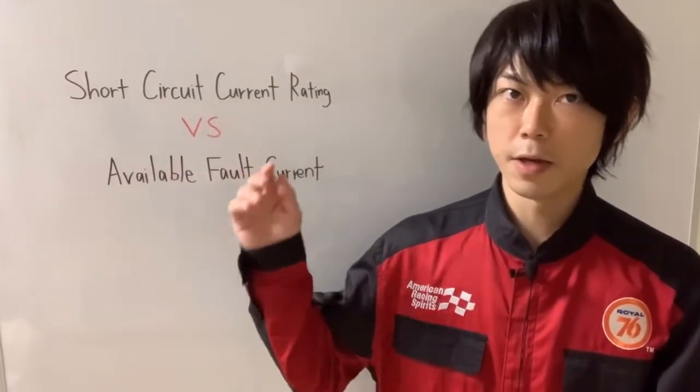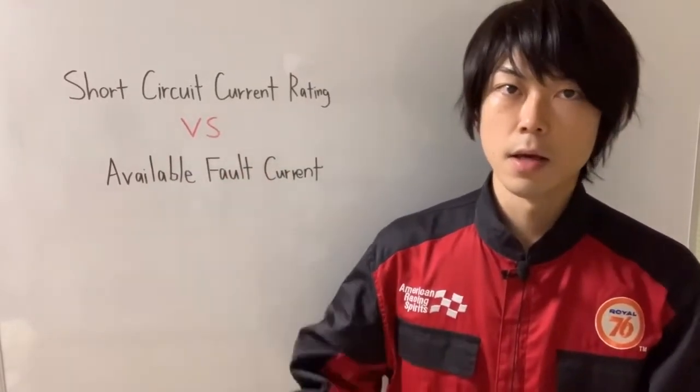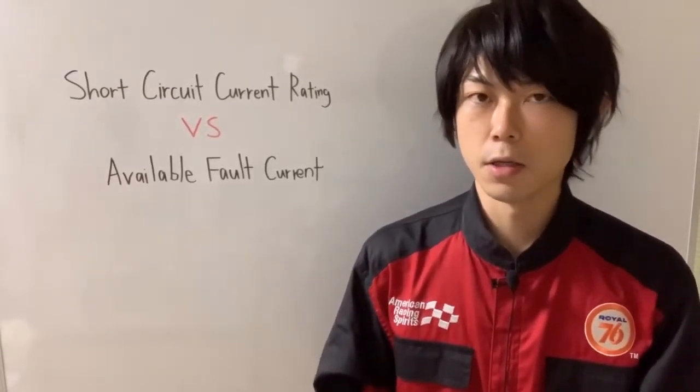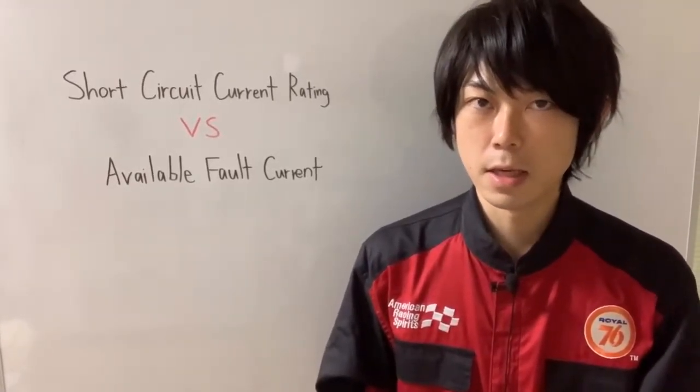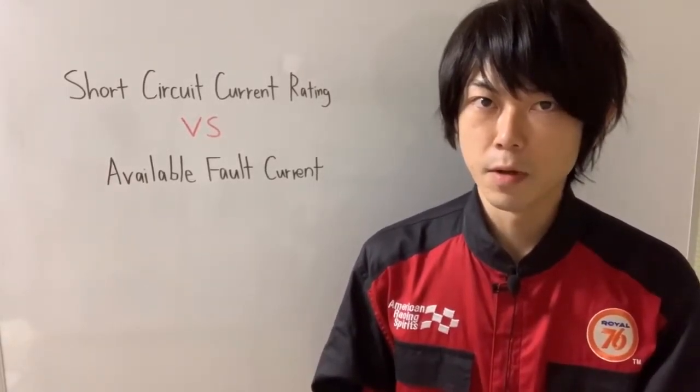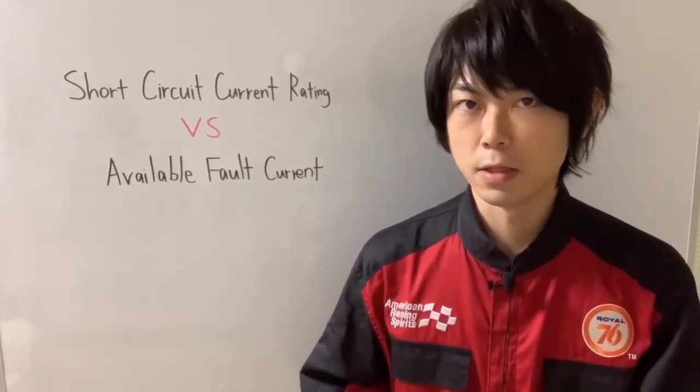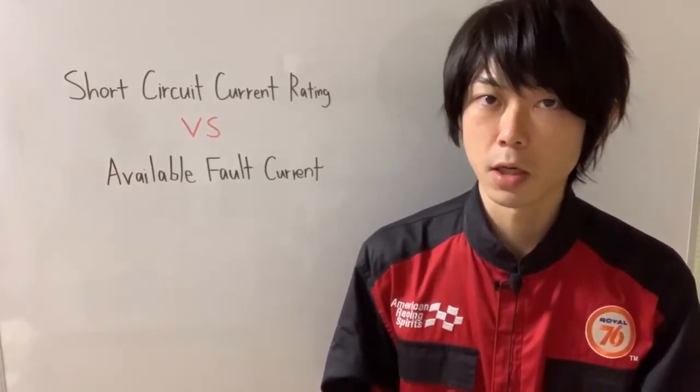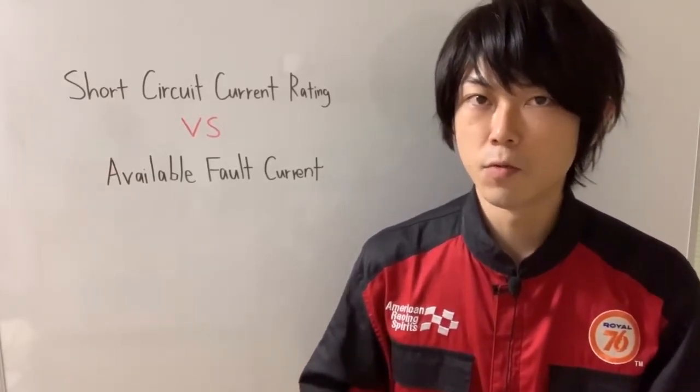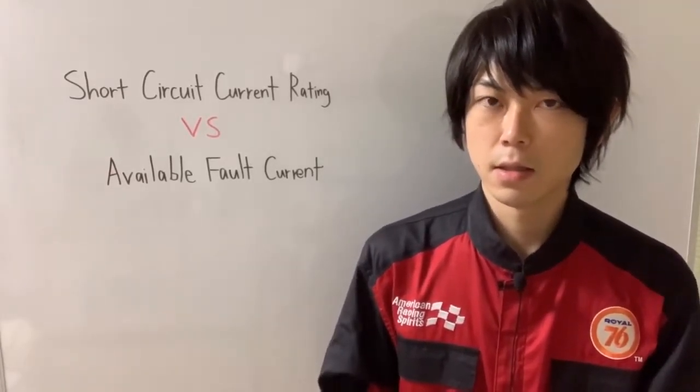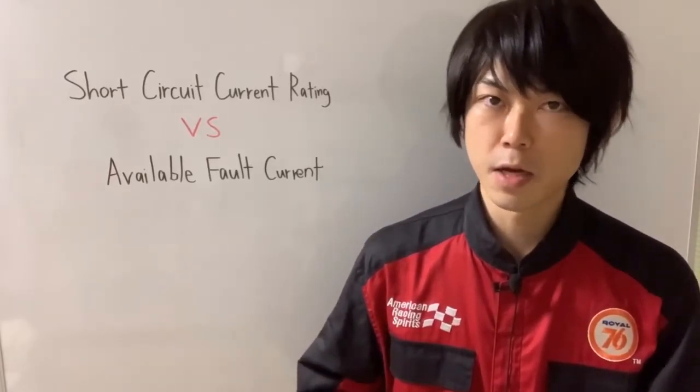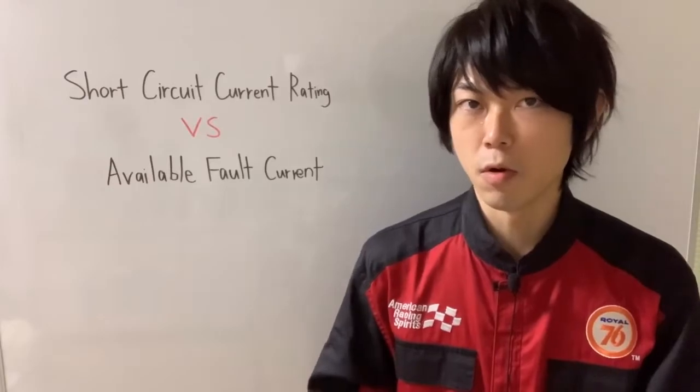Short circuit current rating is an equipment rating, also known as interrupting capacity or interrupting duty for some devices. This rating is the ability of equipment to withstand high levels of current when fault current flows, especially for short circuit. So each equipment must be able to safely withstand this maximum fault current without suffering and experiencing some damage like shock or fire hazard.